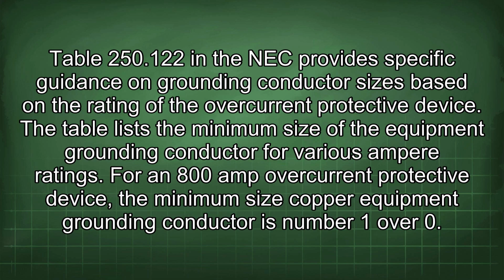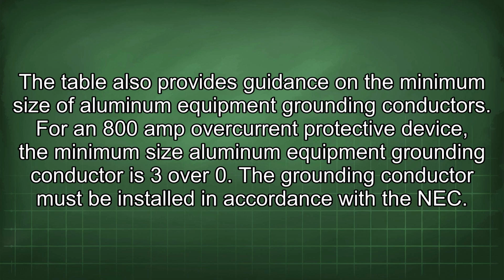Table 250.122 in the NEC provides specific guidance on grounding conductor sizes based on the rating of the overcurrent protective device. The table lists the minimum size of the equipment grounding conductor for various ampere ratings. For an 800 amp overcurrent protective device, the minimum size copper equipment grounding conductor is number 1/0. The table also provides guidance on the minimum size of aluminum equipment grounding conductors. For an 800 amp overcurrent protective device, the minimum size aluminum equipment grounding conductor is 3/0.